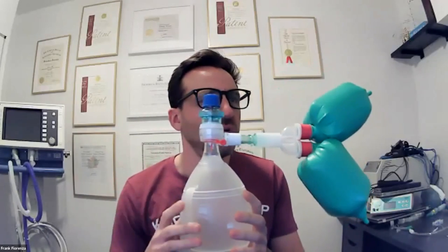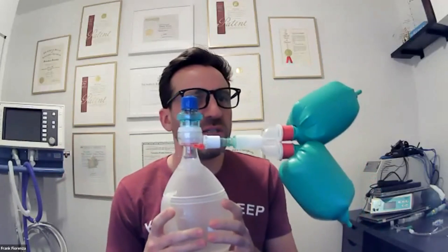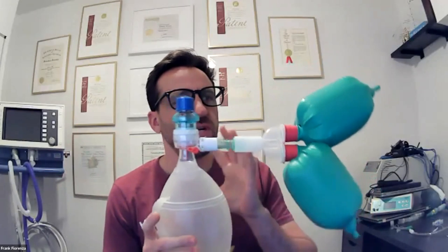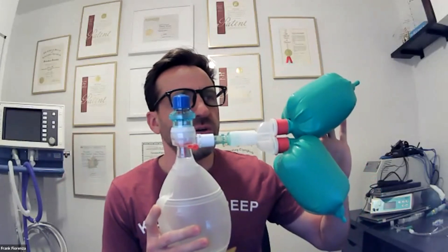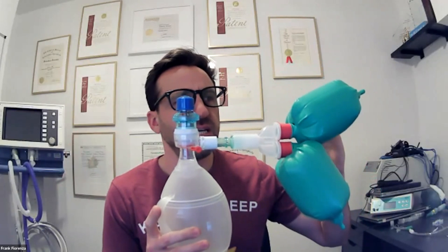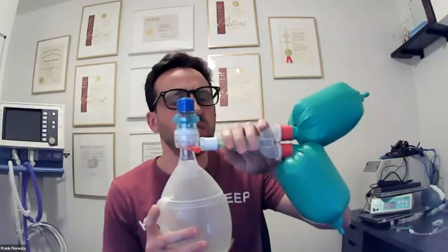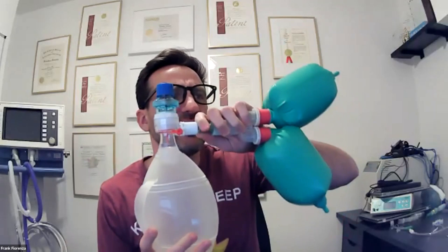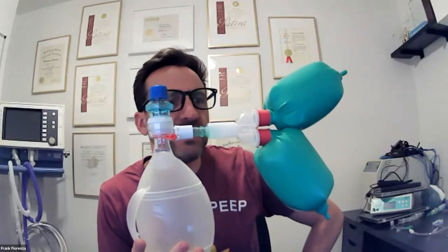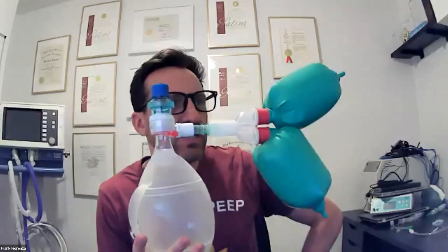In every ICU out there today, we have a nice, lovely, expensive $50,000 PB980 servo, not the Evita 4 that's old and in the back here. So you've got your ventilator giving gas to the patient. Patient's lungs are inflated, everybody's happy. And they say, go to MRI, go to CT, change the HME. So we disconnect quickly, reconnect, and we saw that rapid collapse and then that very, very quick re-expansion, both causing damage.